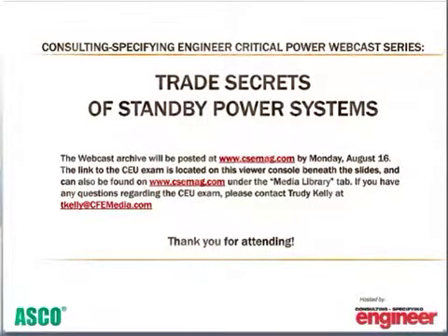Okay. Ken Lovorn? Yeah, I have never seen one. The problem that you get into is the largest transfer switch that you can get is rated at 600 volts. If you start transferring voltages higher than that, you have to have some sort of multiple breaker scheme, and that's really not legally a transfer switch. And so I think I agree with Keith that I wouldn't see that for life safety loads.